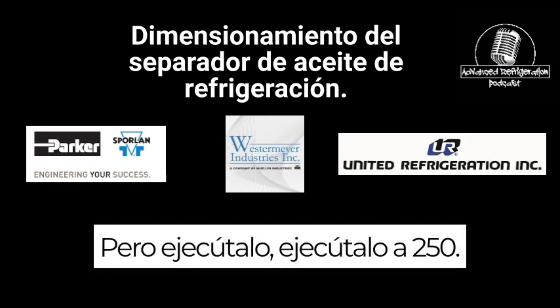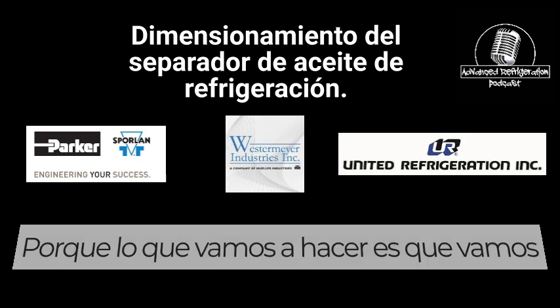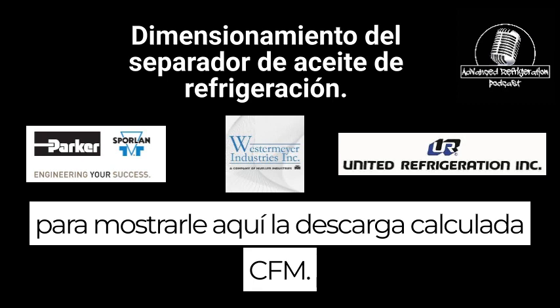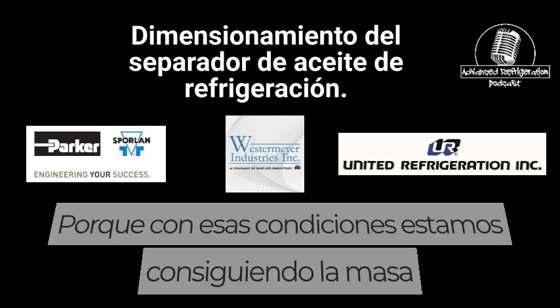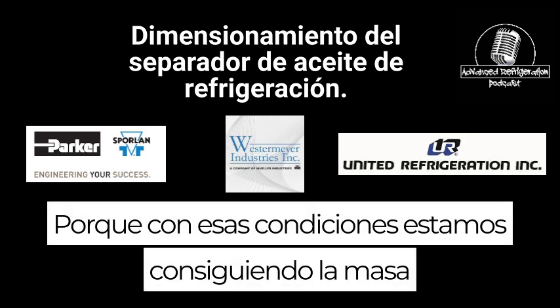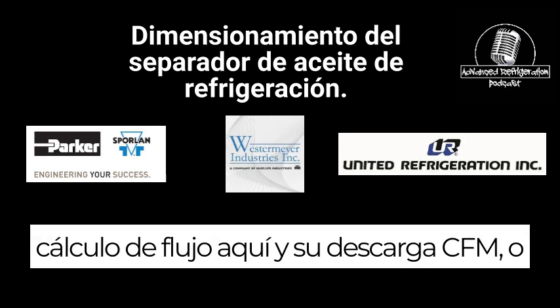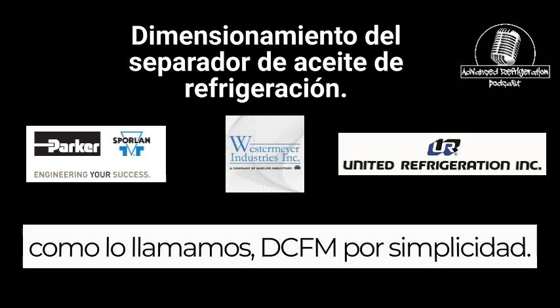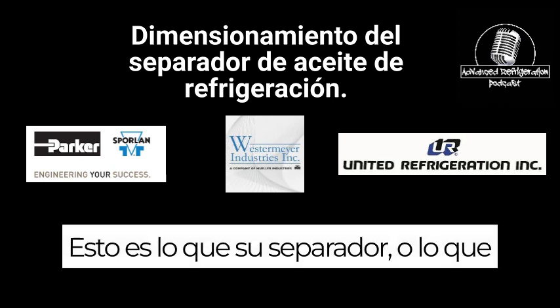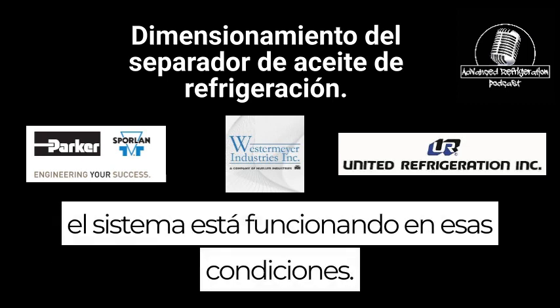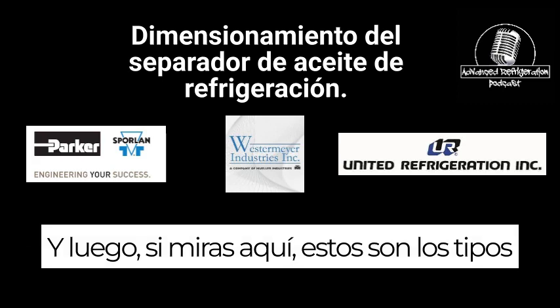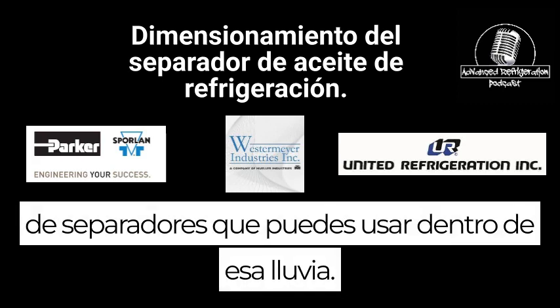But run it at 250, run it at 300. Because what we're going to do is show you here the calculated discharge CFM. With those conditions, we're getting the mass flow calculation here, and your discharge CFM, or as we call it, DCFM for simplicity, is what your separator or the system is running at those conditions. And if you look here, these are the types of separators that you can use within that range.